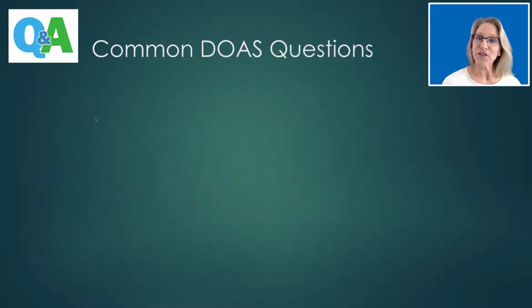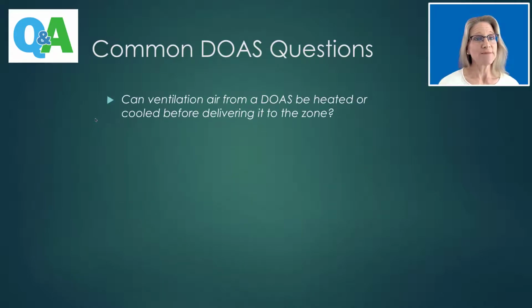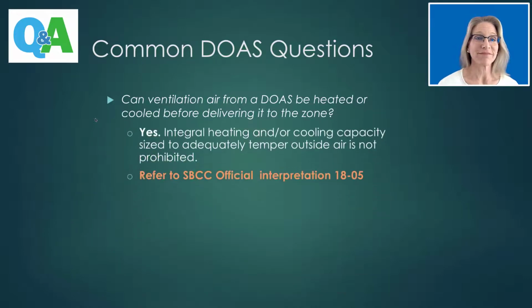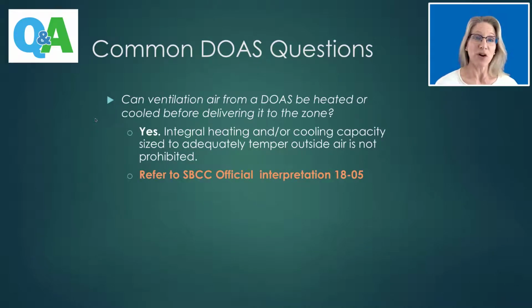So now let's run through a few of the common questions we received through our technical support about the DOAS provisions. Note that these questions are also listed on our WSEC website under FAQs. So first of all, can ventilation air from a DOAS be heated or cooled before being delivered into the zone? The answer is yes. The DOAS unit can have integral heating and cooling as long as it's just sized to handle tempering of outside air. So that's okay, but the actual heating and cooling capacity for space conditioning needs to come from the HVAC system.